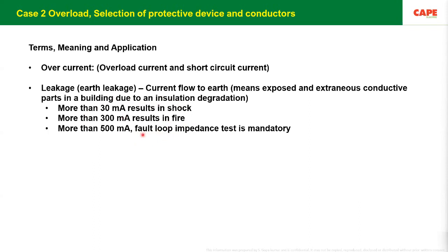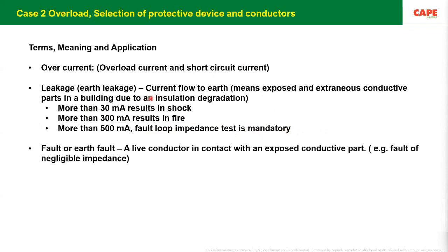So there are 3 subjects with respect to earth leakage. One is to prevent accidents because of earth leakage: you need an RCD or RCCB of 30 milliampere for shock protection, up to 300 milliampere for fire protection, and up to 500 milliampere if you want to avoid a fault loop impedance test. So this is how you are supposed to do overload protection. Similarly, the third one is called a fault. Actually, a short circuit happens between current carrying conductors, between phase conductors or between phase and neutral conductor. But an insulation failure between a current carrying conductor and the earth is called a fault. It is also called an earth fault.